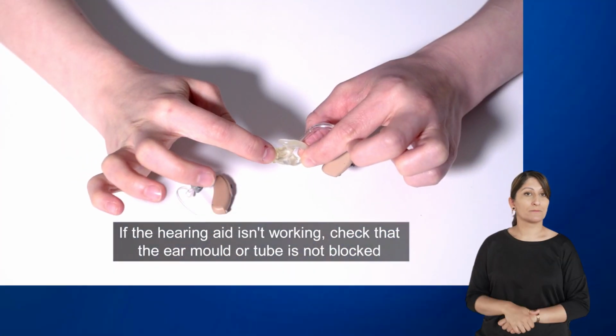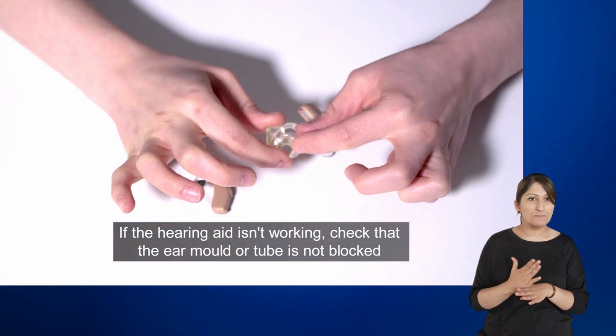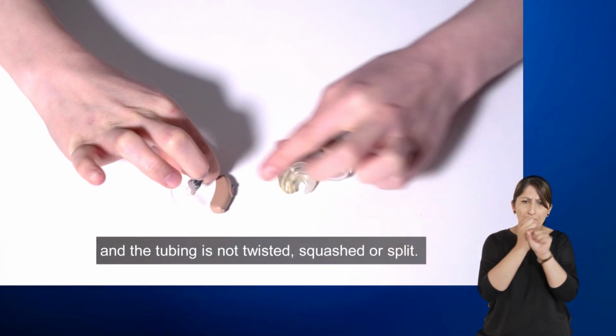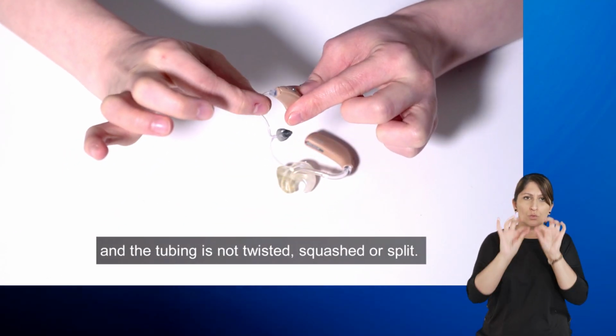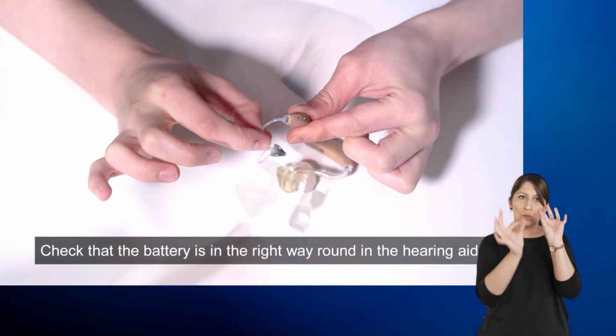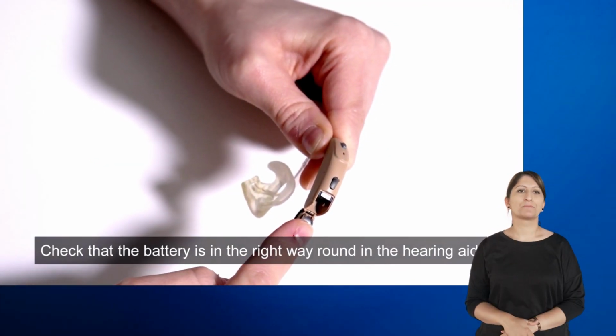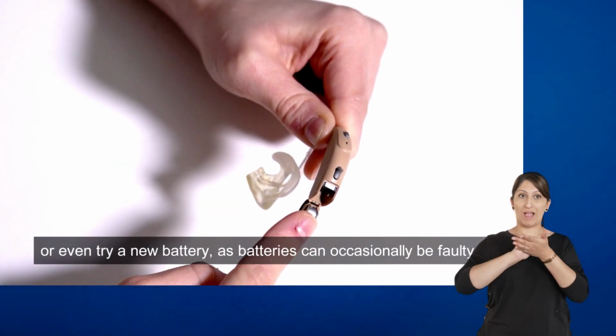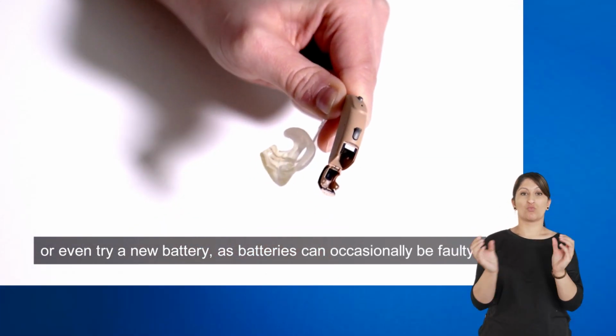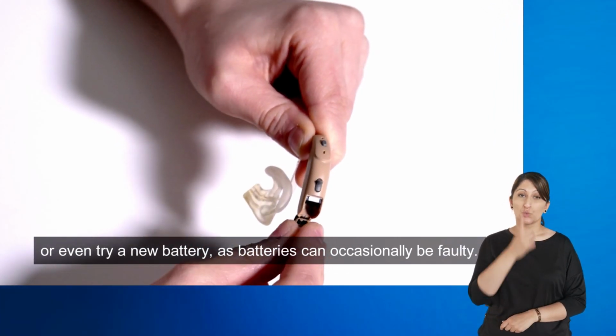If the hearing aid isn't working, check that the ear mould or tube is not blocked and the tubing is not twisted, squashed or split. Check that the battery is in the right way round in the hearing aid, or even try a new battery, as batteries can occasionally be faulty.